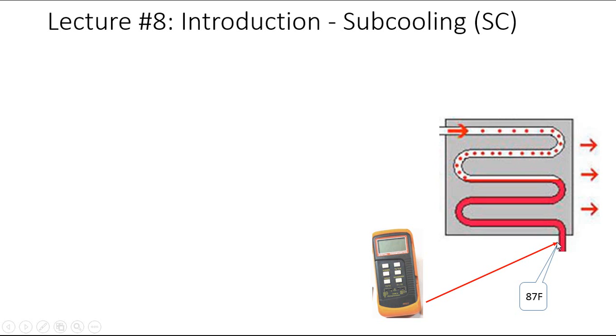And you want to make sure that you use your probe from your temperature device. And you want to make sure you properly attach it to that copper tube. And you want to make sure you insulate it. So in other words, you want to make absolutely sure that your probe is only seeing the physical line temperature, not the ambient air that also surrounds your probe, right? You can usually do that with a little piece of insulation. A lot of times the manufacturers of the probes will give you a special Velcro little package you can wrap around it to make sure you isolate it. But you have to make sure it's properly isolated, insulated.